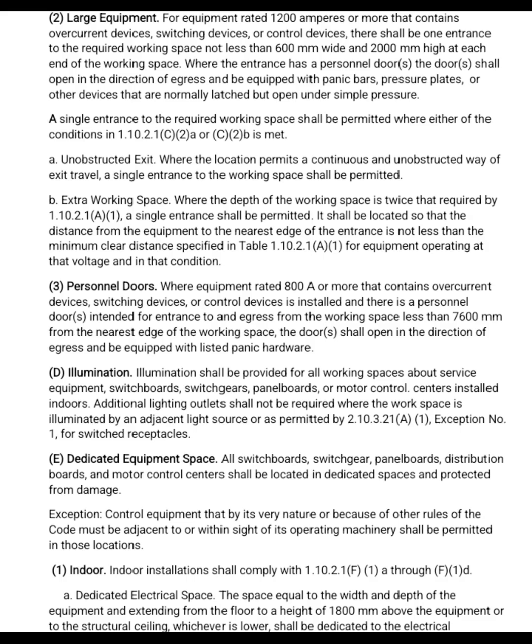A single entrance to the required working space shall be permitted where either of the conditions in 1.10.2.1 C2A or C2B is met. A. Unobstructed exit. Where the location permits a continuous and unobstructed way of exit travel, a single entrance to the working space shall be permitted. B. Extra working space. Where the depth of the working space is twice that required by 1.10.2.1(A)(1), a single entrance shall be permitted.